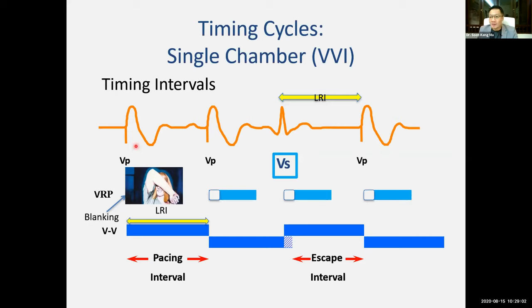So if that's the case, then you better have a blanking period. If not, then you will saturate your sensor up to a level that for it to recover, it may cause a problem. So the blanking period is designed to protect the pacemaker from seeing for that very moment. After I deliver a spike, I stop seeing, blank myself for a short period of time.